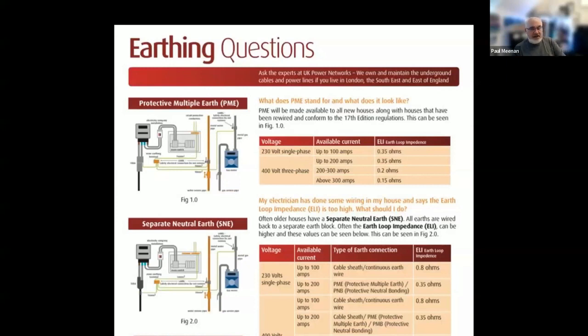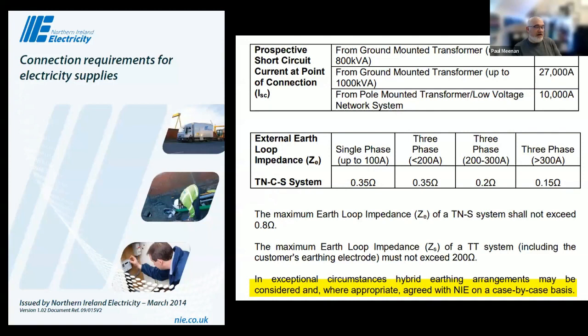We have what we call PME, protective multiple earth, also known as TNCS, and a separate neutral and earth, also known as TNS. And the networks originally were TNS. They're now pretty much all combined neutral and earth, unless they're on a private transformer. Personally, I think separate neutral and earth was always the way to go. But just to let you know, some DNO companies will allow a hybrid. So the photo you'll see in a minute is a hybrid of multiple earthing systems. It can be confusing for an electrician when they're trying to ascertain what it is. I've always said go for the worst case.